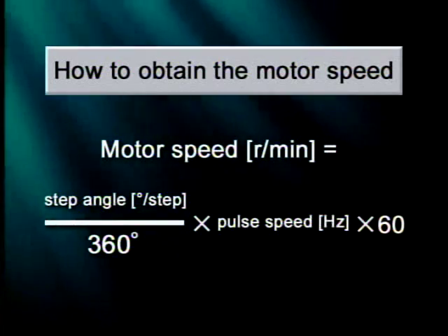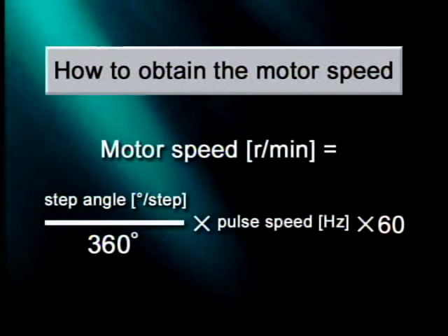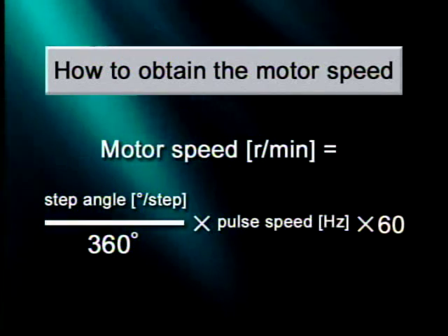You obtain the motor speed with the following formula. Motor speed in revolutions per minute equals step angle divided by 360 degrees times pulse speed times 60.